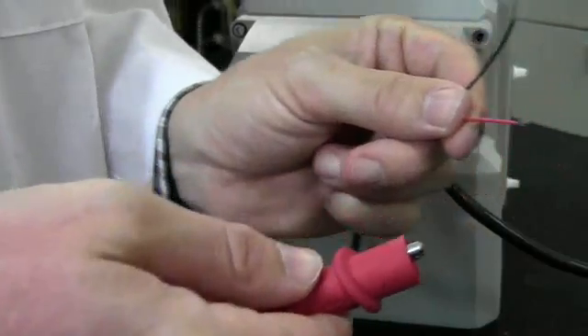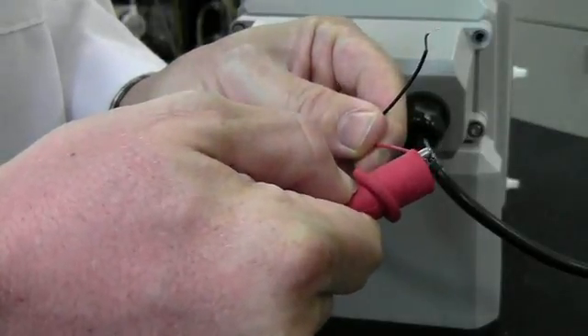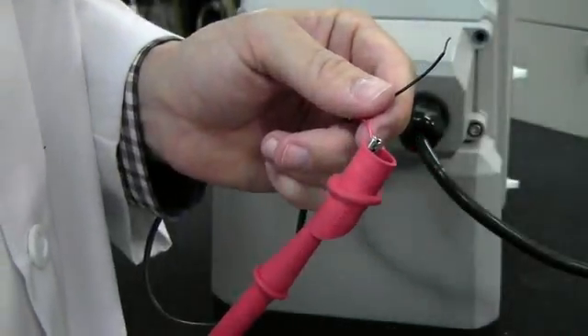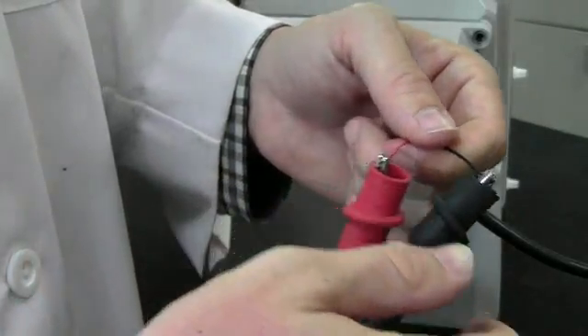After the pump has been configured for the 4 to 20 milliamp signal, and the 4 to 20 milliamp wire is connected to the terminal board, we can use a 4 to 20 milliamp signal generator to test the pump. Here a Fluke device is being connected to the 4 to 20 milliamp cable.